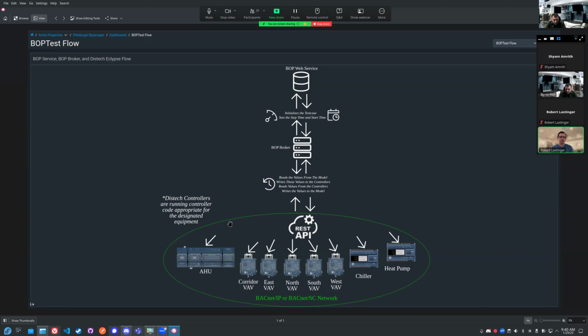On top of that, the controllers are talking to each other via BACnet. In this case, the VAVs and the air handler are running G36 sequences, so all the communication between them, the sharing of data for that sequence, is happening in real time, fed by data from BOPTest. The VAVs tell the air handler things like damper position, room temperature, CO2 load, and the air handler tells them discharge air temperature and what to do. It's like a real project, a real building—except I can do whatever I want with it.